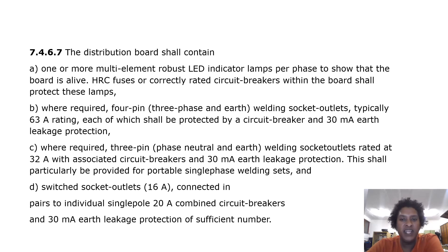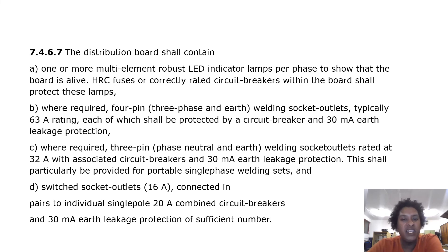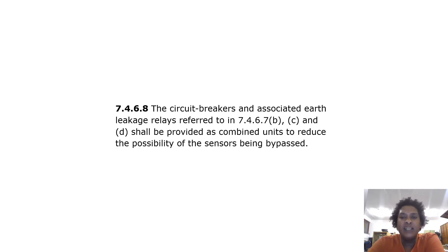Where required, four-pin three-phase and earth welding socket outlets, typically 63 amp rating, each of which shall be protected by a circuit breaker and 30 milliamp earth leakage protection. We require 3-pin phase, neutral and earth welding socket outlets rated at 32 amp with associated circuit breakers and 30 milliamp earth leakage protection. This shall particularly be provided for portable single phase welding sets, and switched socket outlets of 16 amps connected in pairs to individual single pole 20 amp combined circuit breakers and 30 milliamp earth leakage protection. The circuit breakers and associated earth leakage relays shall be provided as combined units to reduce the possibility of the sensors being bypassed.